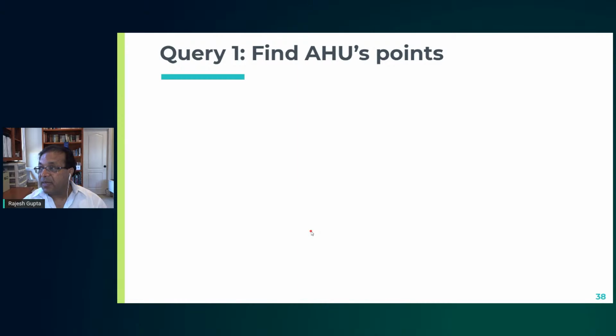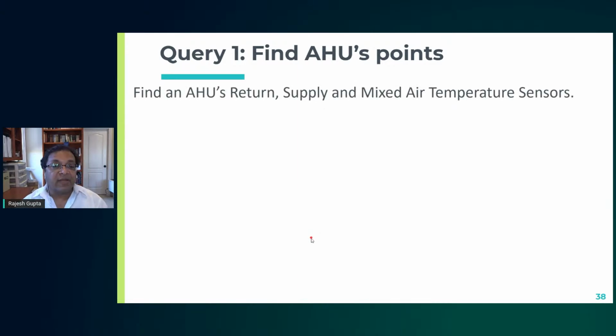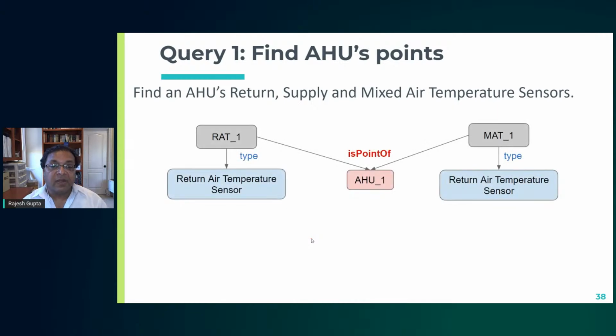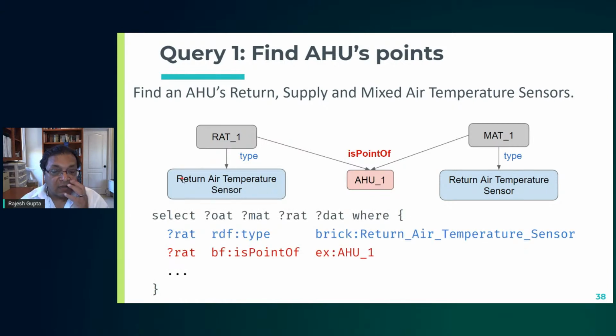So the program is nothing but finding the building level water usage, finding the AHU points, finding corresponding VAV points. Remember, you're writing a program that can go from one building to the other. So each of these needs to be discovered for other buildings as well. And so when you do that, your query could be: find all the returns of the temperature, the return, supply and mixed air temperature. So this is AHU. You look at the temperature sensors of that kind, and this is the relationship you're looking for. That leads to a query of this kind, where you're looking for a return air temperature and you want to return it for a given particular AHU. So this is the particular AHU for which you're selecting the return air temperatures.